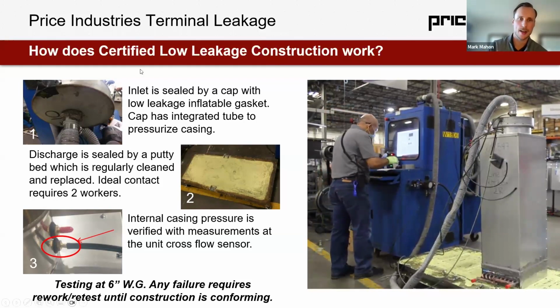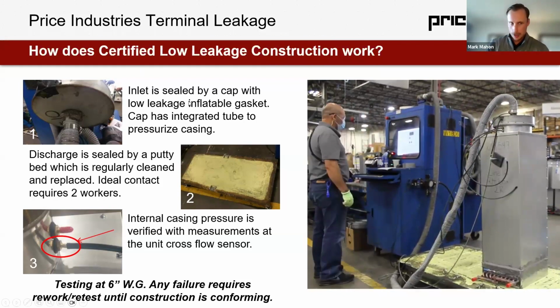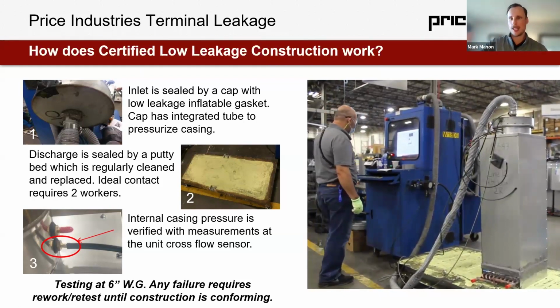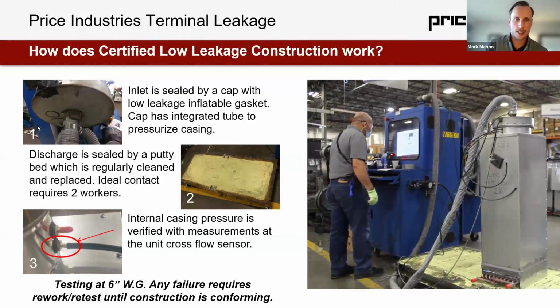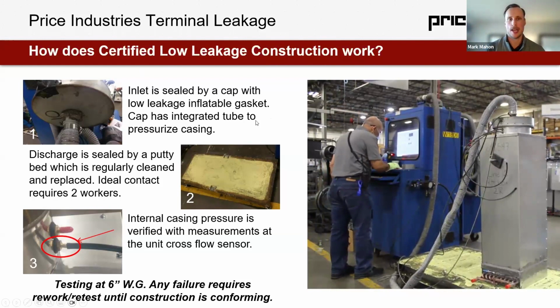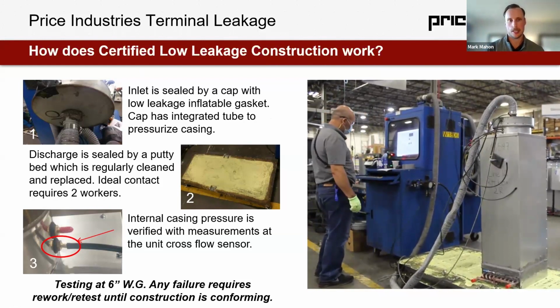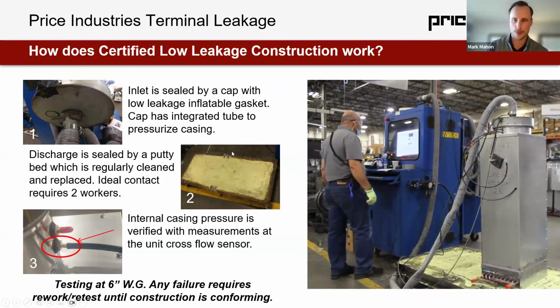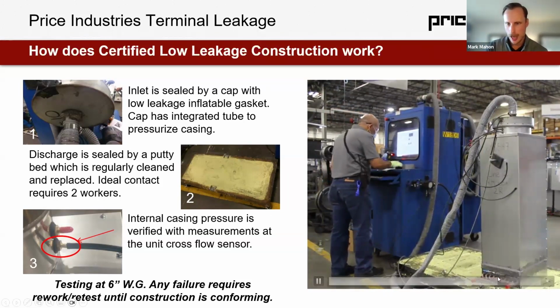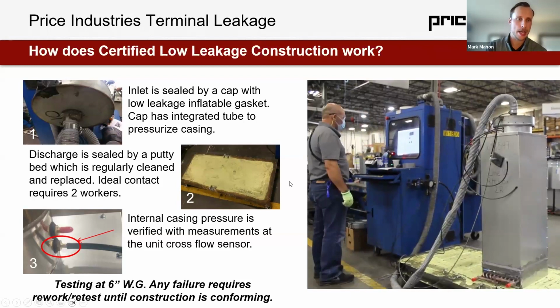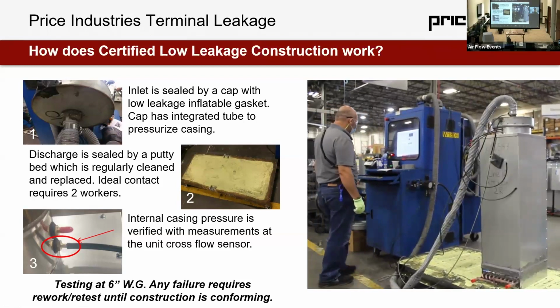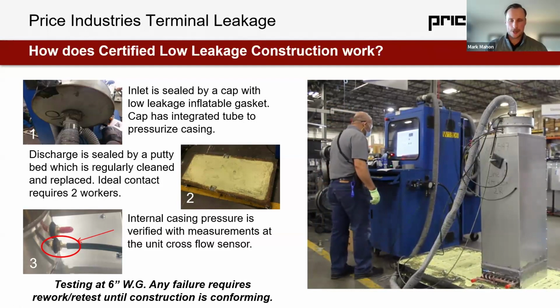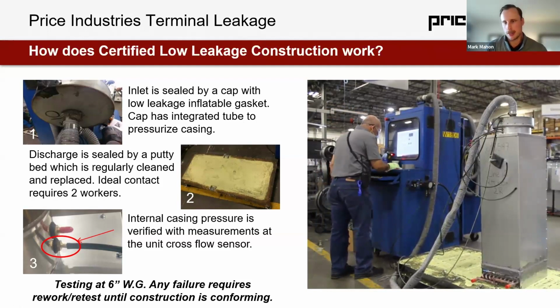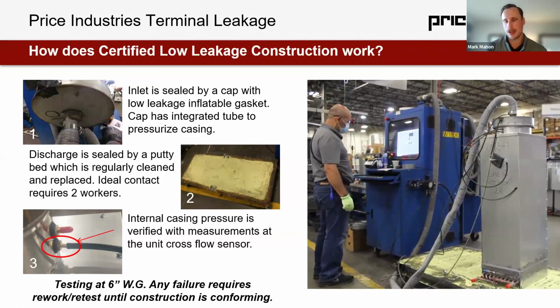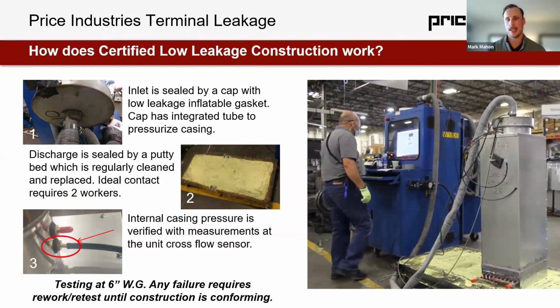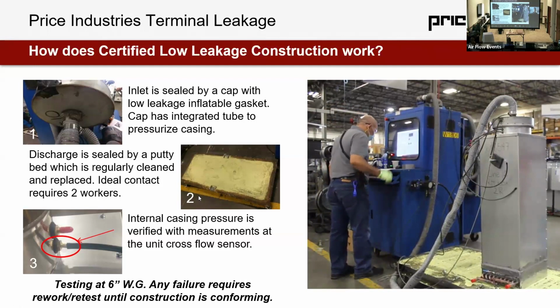The inlet is sealed by a large cap. This is like the low leakage cap that you would put on when pressure testing ductwork in the field. It has an inflatable gasket, so it makes a very strong low leakage seam, and that's what allows for the pressurization of the casing. The other thing is this very gross yellow putty bed. It's a 4-inch deep bed of putty that we push the seam and the connection of the terminal into, to create a really good mate and seal on the discharge side of the equipment.